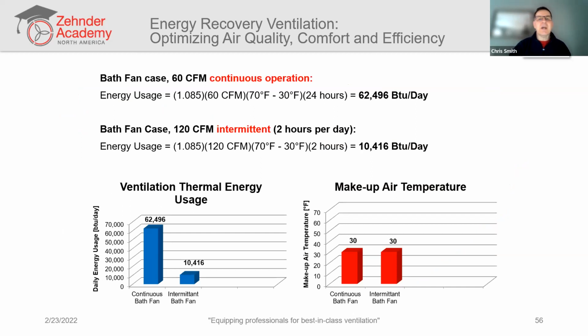So if we're using a bath fan, let's say we're using a bath fan in 2 different scenarios. Let's say the first scenario is a bath fan being used at 60 CFM in continuous operation, 24/7. It's being used in order to achieve the required continuous ventilation rate of 60 CFM. So that's going to result, if we run our calculation, in a little more than 62,000 BTUs per day of thermal energy usage. So that's the energy penalty of using that bath fan.